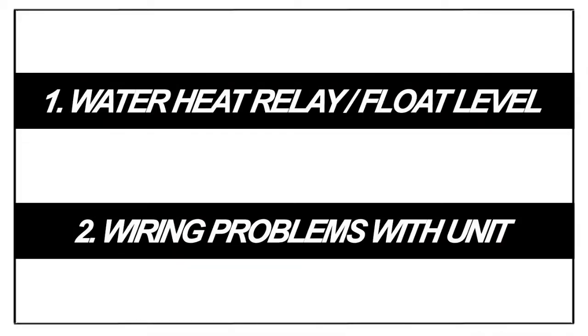Turning on the water heat relay in service and diagnostic mode is independent of any float level logic and therefore does not require any specific float level, or for that matter, it doesn't even need to have a float present. If only motor amps are seen when either air or water heat relays are turned on, then there's probably a bad part or a wiring problem in the unit.